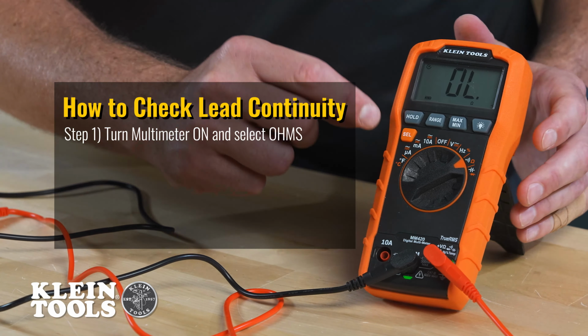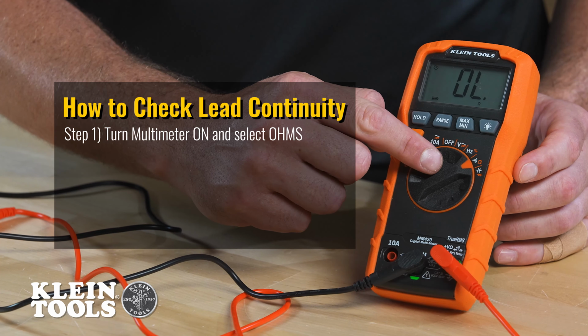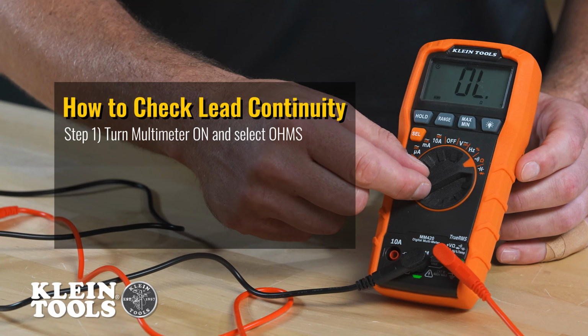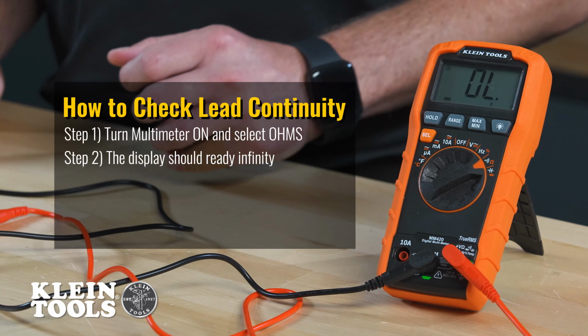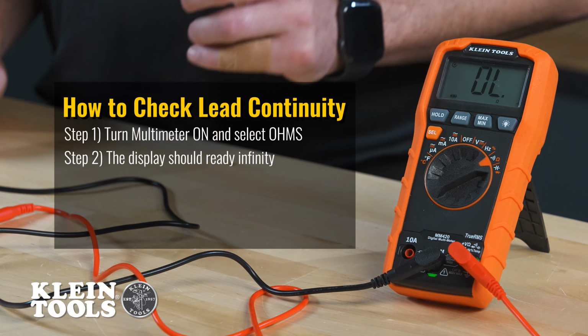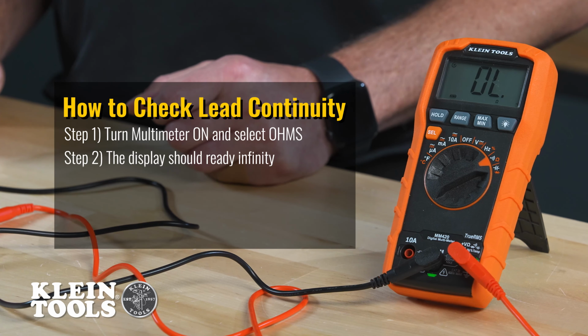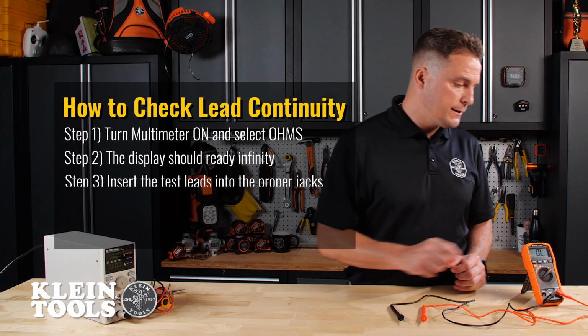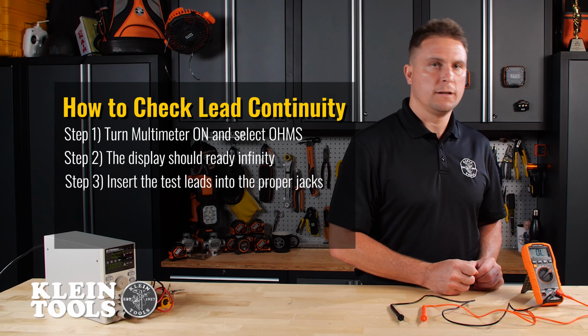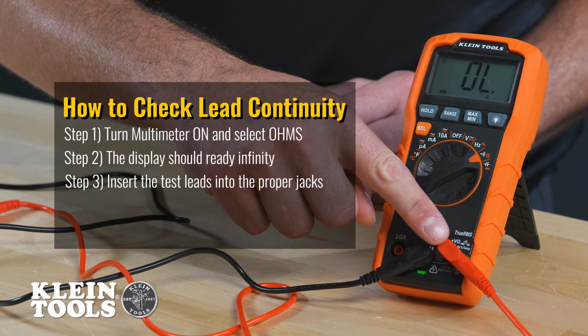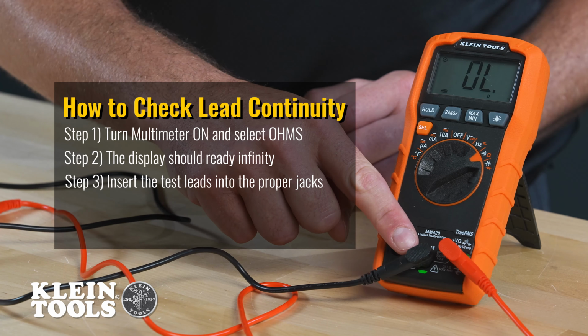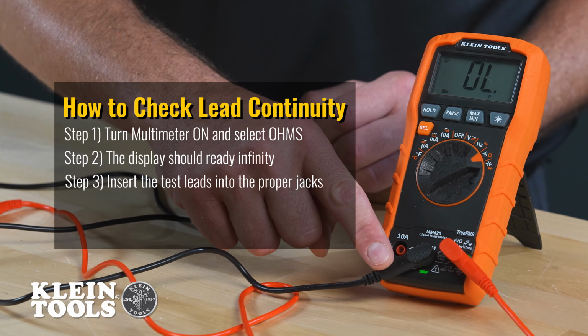Step number 1. The multimeter should be turned on and set to the ohm setting, which we've already done for you here. Step number 2. The display should read infinity and OL should appear on the display. Step number 3. Insert the test leads in the proper jacks. The red lead goes into the red ohms jack. The black lead goes into the black common jack.